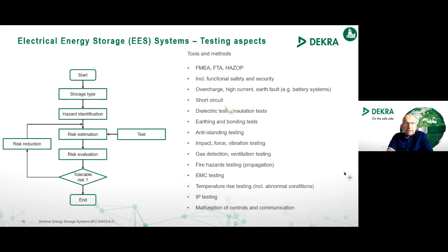On the right-hand side, you see different areas where you may have to perform testing. In the electrical area, you may have to do short circuit testing, dielectric verifications, check the earthing and bonding, and also a special test for storage systems, anti-islanding testing. That's the case where the grid is down and the storage system may provide power to the grid.